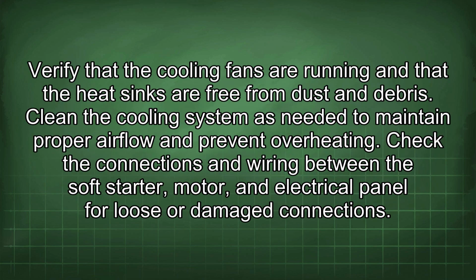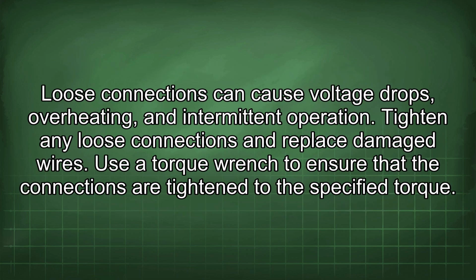Verify that the cooling fans are running and that the heat sinks are free from dust and debris. Clean the cooling system as needed to maintain proper airflow and prevent overheating. Check the connections and wiring between the soft starter, motor, and electrical panel for loose or damaged connections. Loose connections can cause voltage drops, overheating, and intermittent operation.